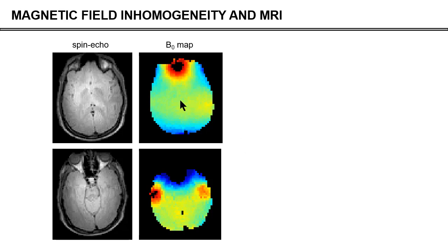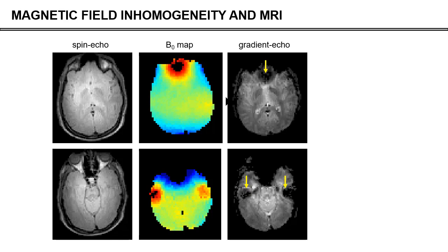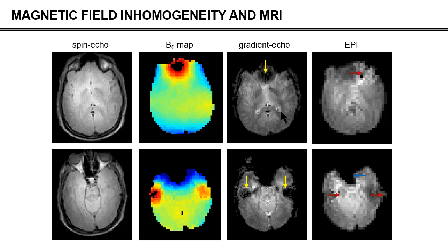How about for MRI? If you do spin echo MRI, the inhomogeneity actually has very little effect — even with very strong inhomogeneity, the MRI is just fine, because spin echo sequences aren't sensitive to inhomogeneity. Unfortunately, not all MRI can be done with spin echo methods. Most fMRI is done with gradient echoes, and if you run a gradient echo you do have severe signal loss exactly in the areas close to air-water boundaries, which could be a problem if you're interested in, for instance, the frontal cortex. If you combine this with ultra-fast imaging such as echo planar imaging, then on top of the signal loss, you're also going to get image distortion, where pixels appear at spatial locations where they don't belong.